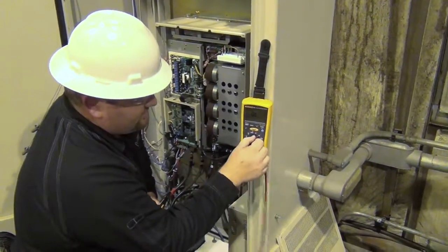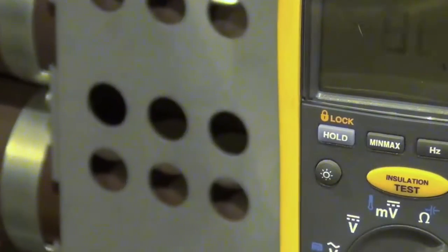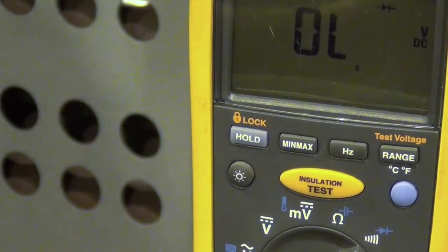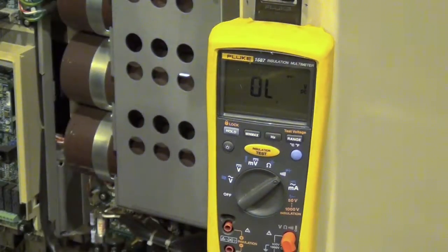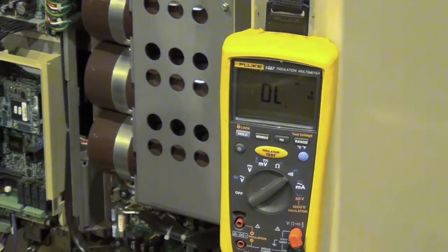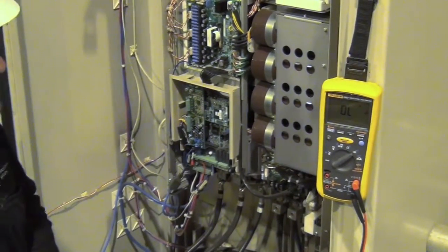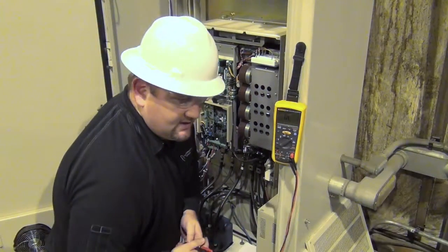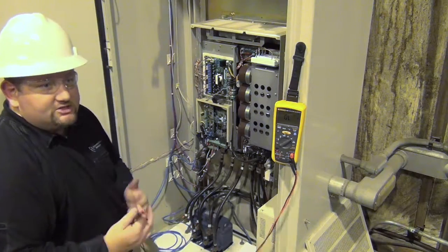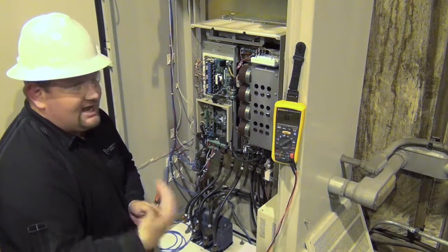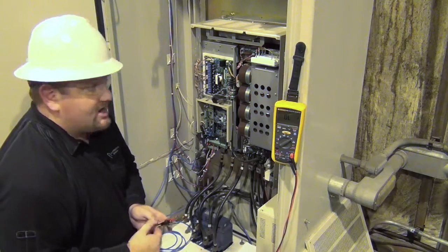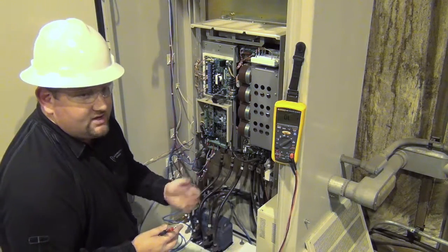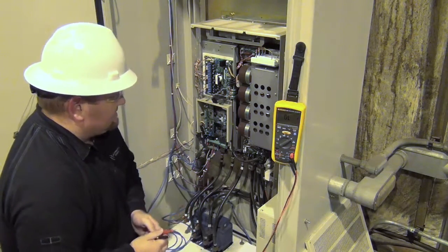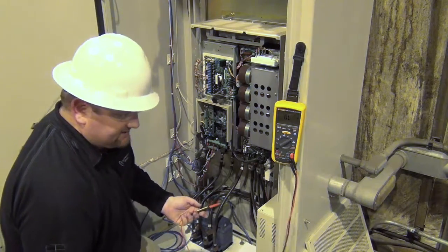you have the diode symbol, so we're going to put it in and we have to press the blue button to get a diode check. In order to run this check on a drive, you have to have a drive that has both your DC minus and your DC positive from your DC bus available to you. Smaller drives, generally micro drives, 25 horsepower or so in that range, they may not have the terminals for plus and minus brought out to an accessible location. So obviously if you don't have access to those terminals, you can't perform this test.